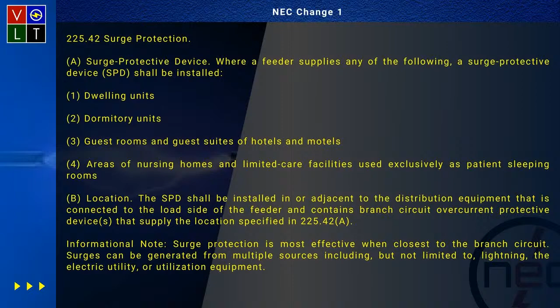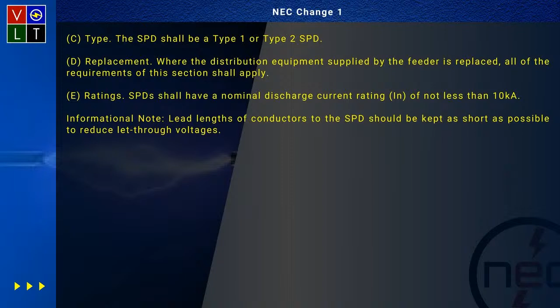And then they tell you the location - it'll be installed at or adjacent to the distribution equipment, and then they tell you the different types, like we were discussing, Type 2 for those multifamily units. Then it talks about replacement - where you have distribution equipment supplied by a feeder, it tells you all the requirements in this section shall apply. Then it talks about the rating, and it won't be less than 10 KA. That's it, so for me it's an okay change - I actually already have it at my place, so I'm not worried about it. I think it's fine, an okay change.